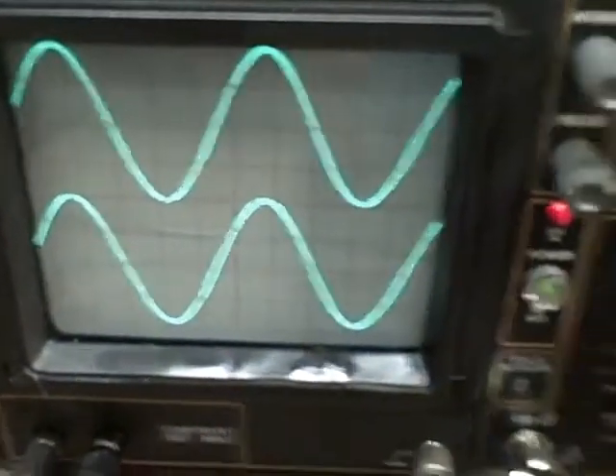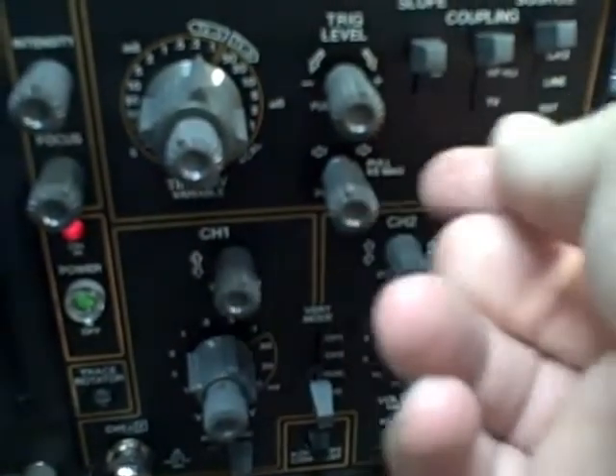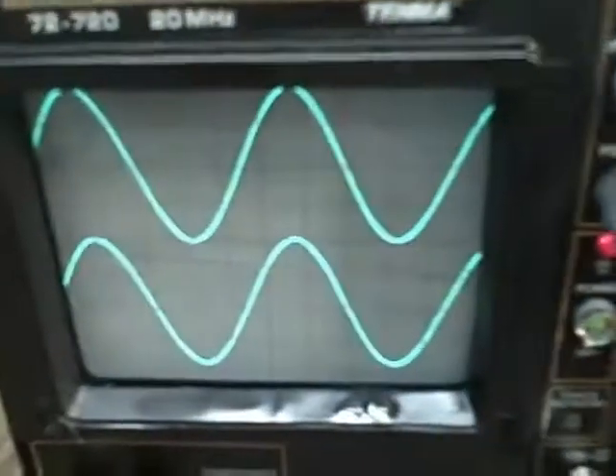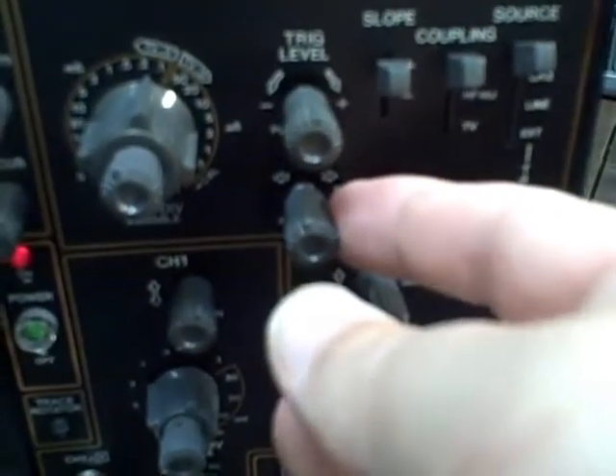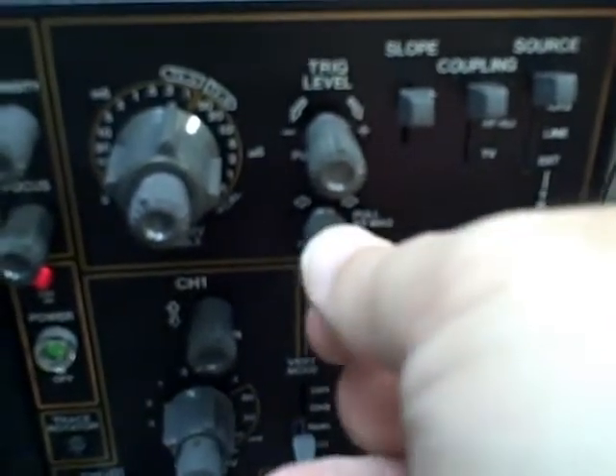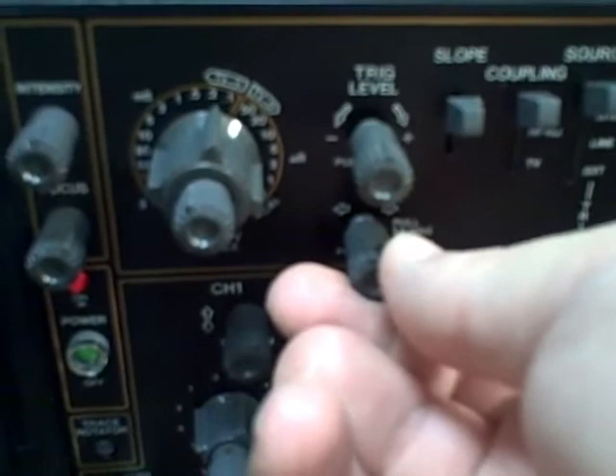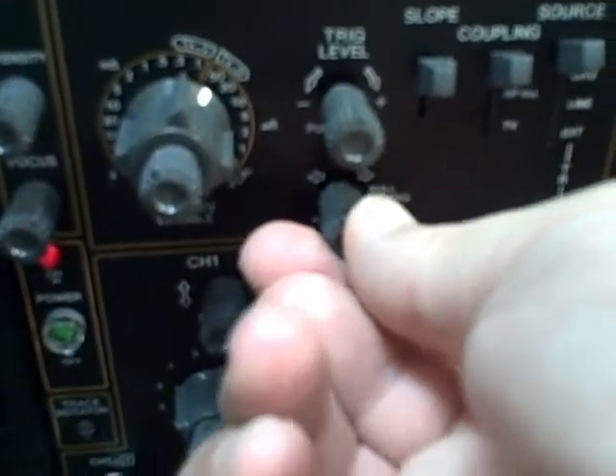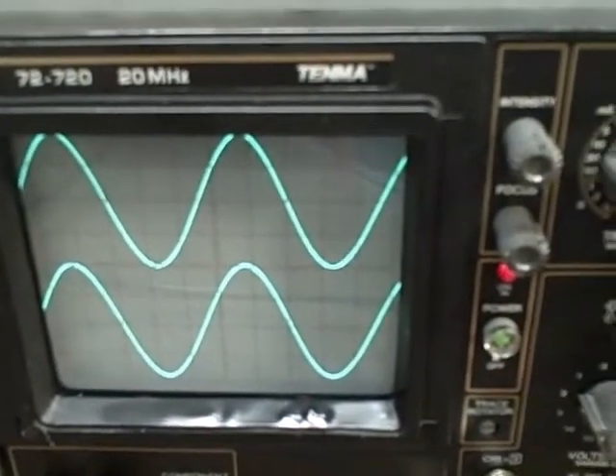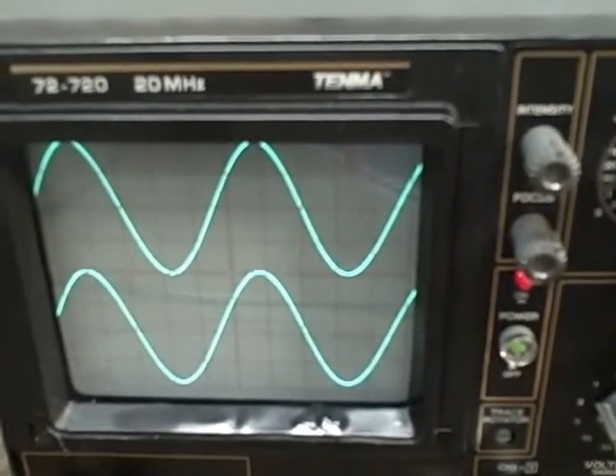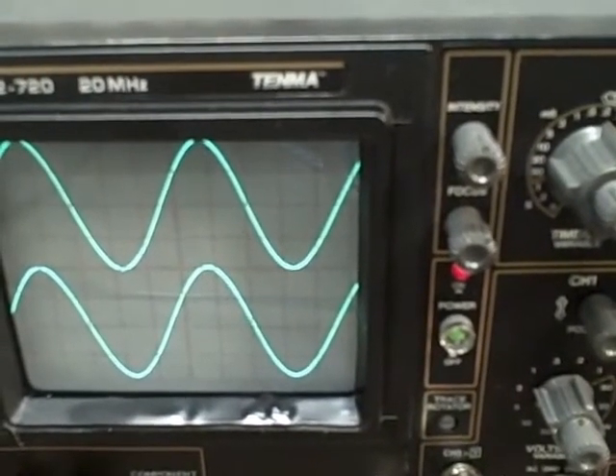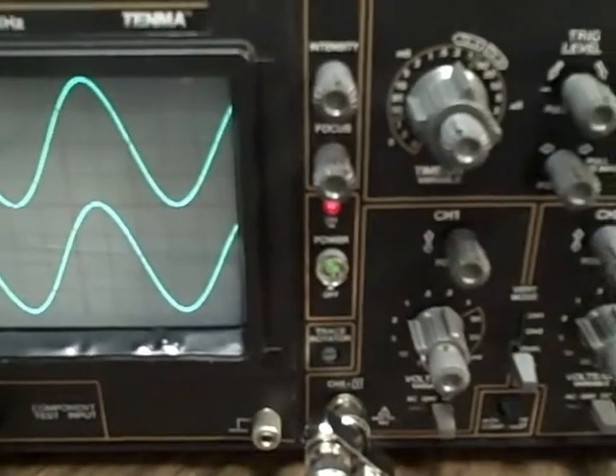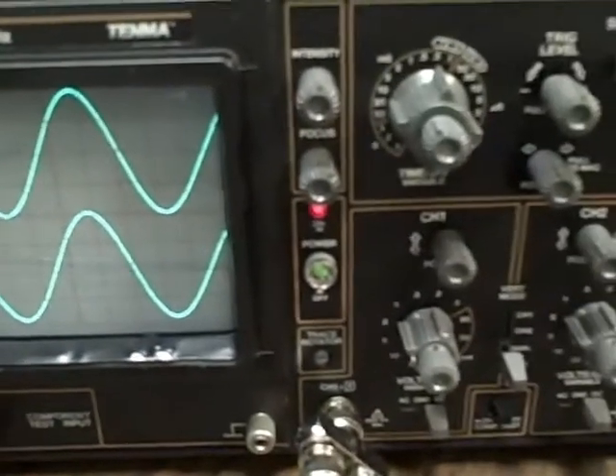About the only thing on the scope that isn't functional on this front panel is the magnification of the horizontal. Supposedly you can pull this out and increase the magnification times five, it does not function. I have tested the switch, the switch is fine, the terminals on the board are fine, we have something at board level that's not working and I don't have a circuit to follow so I kind of backed off on it. It isn't something that I use often, almost never to be honest about it, but every other function on the scope seems to be working well. We'll give it a series of tests to prove that.